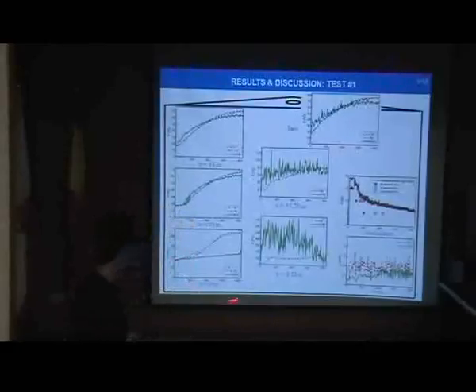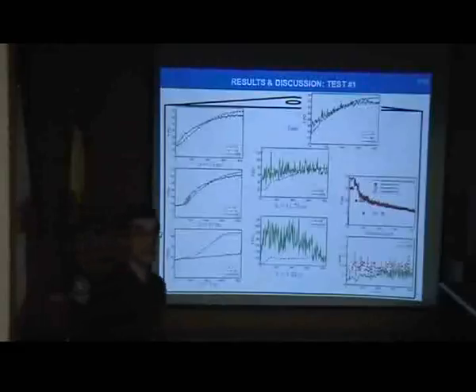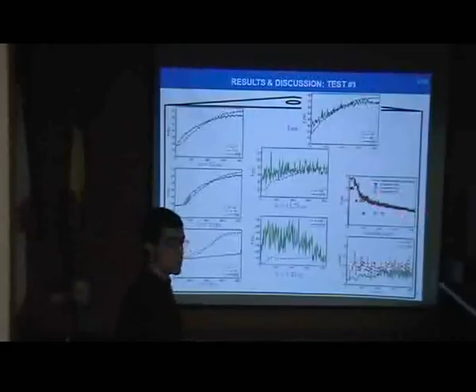However, at the lowest location in the near-the-wall region, 5 meters high, FDS under predicts the smoke temperature by even more than 50%. Therefore, as a consequence, the final smoke layer height has been also over predicted.